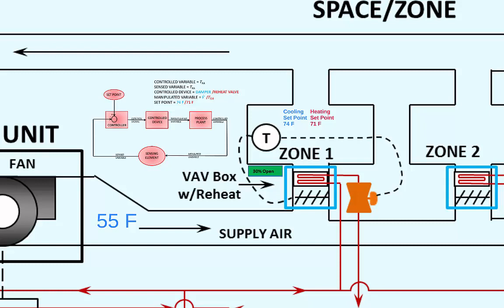When in cooling mode, the damper modulates and we maintain a constant supply temperature of 55 degrees Fahrenheit. When in heating mode, the airflow rate provided to the space stays constant, and we modulate the supply temperature by use of the reheat coil.